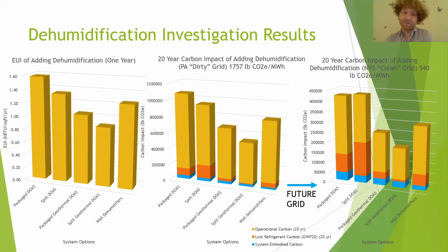Packaged geothermal does really well. Split is even better. The wall dehumidifiers come in the middle, because they're only treating the room—they're watching the humidity right there, so they're not dehumidifying quite as much. It's more about controls than actual unit efficiency. So even though they're a little less efficient, being just a small unit in each apartment, they get the benefit of not dehumidifying when they don't have to, whereas a packaged system on the roof can't always hit exactly the right spot.